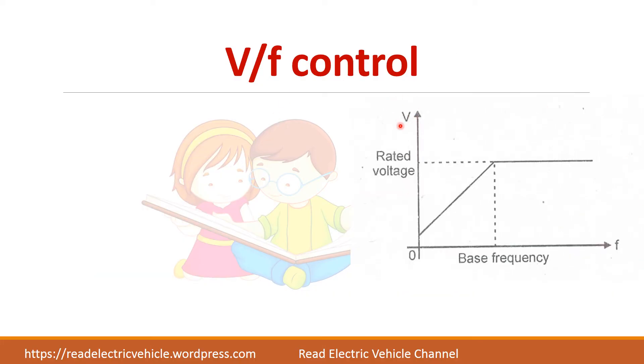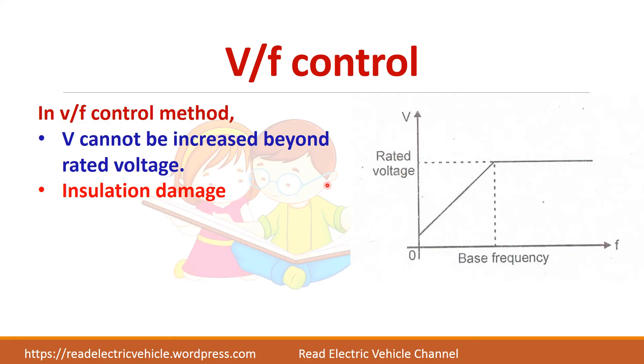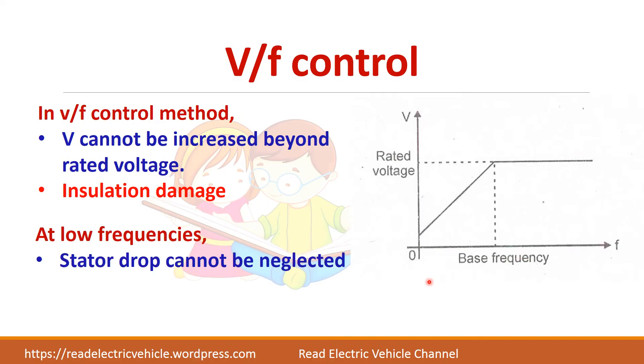Looking at the graph between V and F, the V by F ratio is maintained constant up to the rated or base frequency. Once the base frequency is reached, voltage must be kept constant, because increasing voltage above the rated value would cause insulation damage. So it is necessary to stop increasing voltage and keep it constant after base frequency.